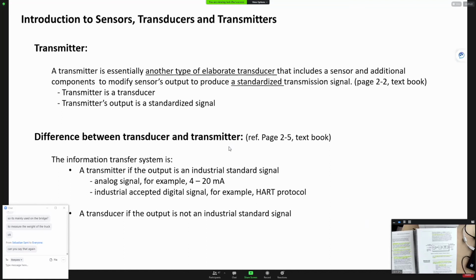Okay, so all transmitters belong in the transducer category. But to be able to call a transducer a transmitter, it has to give out an industrial standard output signal. So if a transducer can supply 4 to 20 milliamps or 0 to 10 volts, or any type of digital output signal, it can be called a transmitter.